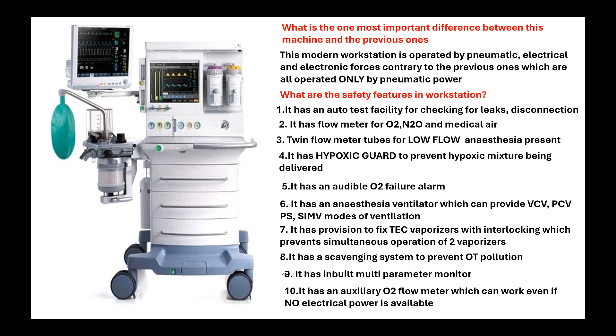This is the question I asked in the earlier slide. Okay, so here you have an auxiliary flow meter. There are two here. Can you see two auxiliary flow meters with control knobs? What is that for? One for oxygen and one for air. Okay, they are giving provision even for air also. And they can operate even if the power is not on. That is the main safety feature of that. So you don't require electrical power for delivering gases or oxygen through the auxiliary flow meter. So many features are there.